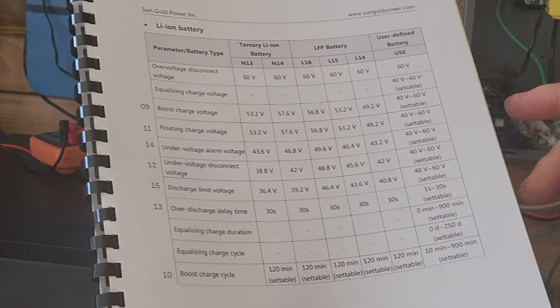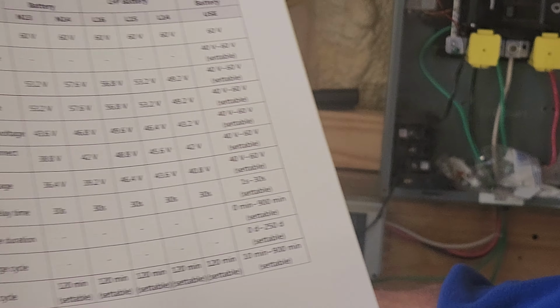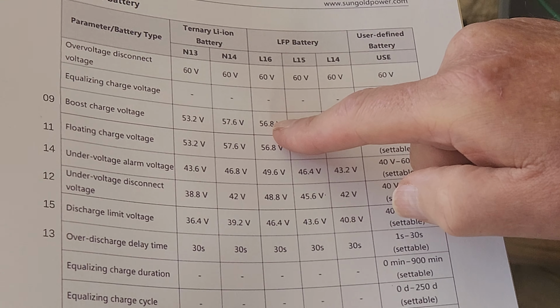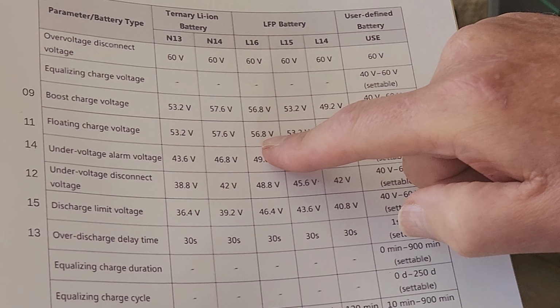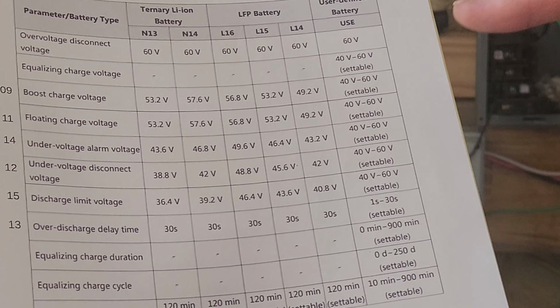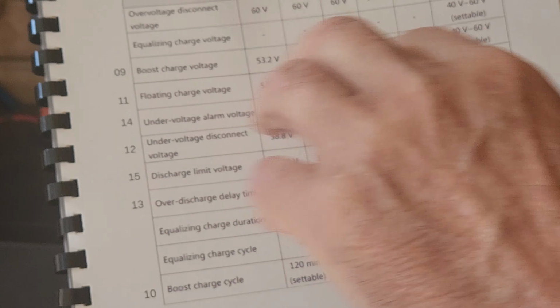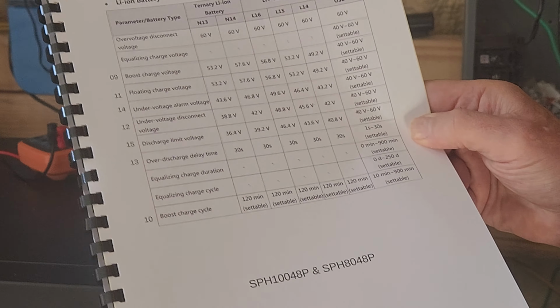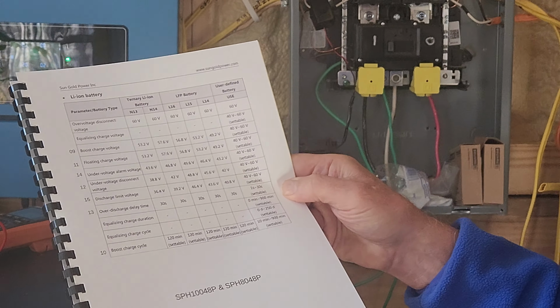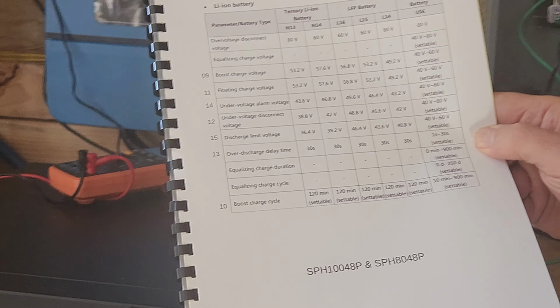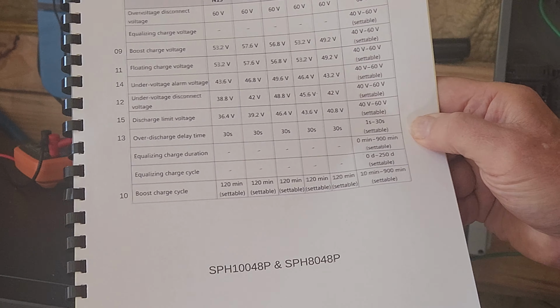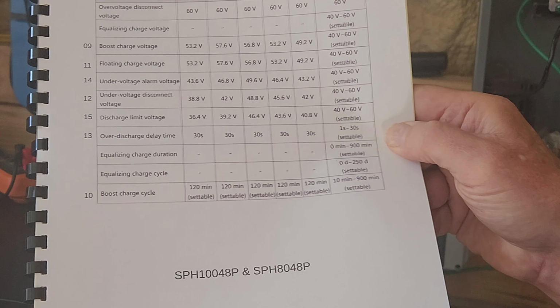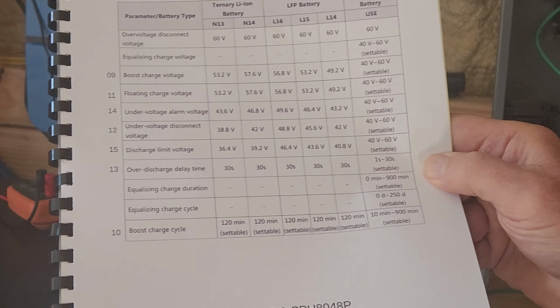To balance or calibrate this, what I had to do was change the boost charge voltage and the floating charge voltage to 58.4. What this does is give more power, more voltage at first, and after a 2-hour time limit it lowers the voltage to extend battery life for lead acid and gel batteries. But that's a feature you don't really need for lithium ion, so if you set the boost and floating voltage the same, you essentially get rid of the boost feature.